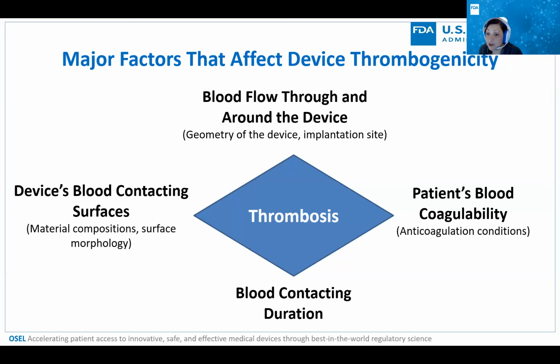There's a couple of things that do affect the thrombogenicity of medical devices. So the first one is the blood flow around the device. So what's the geometry of the device? Where is it implanted? It's also dependent on the surface or the material itself, where the device is coming in contact with the blood, and any surface morphology associated with that, how long it's in contact with the blood, and then it's also patient specific. So if they're on any anticoagulants or anything like that, that would have to also be taken into consideration.